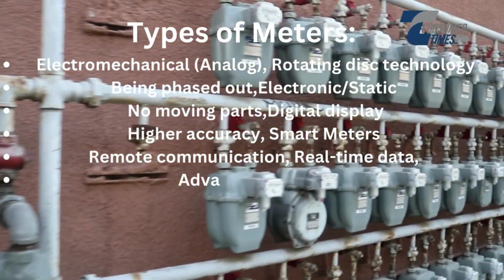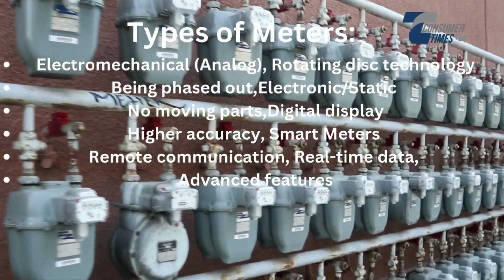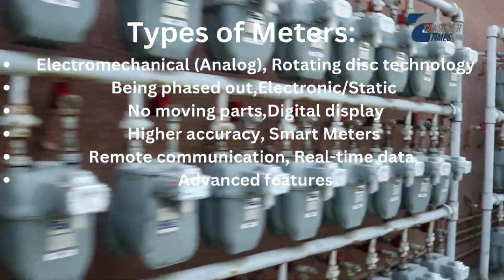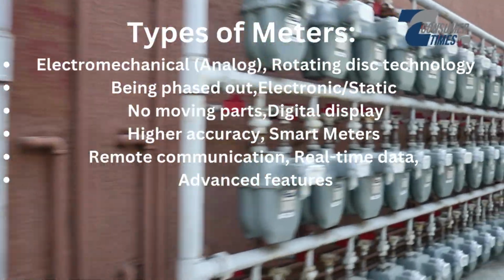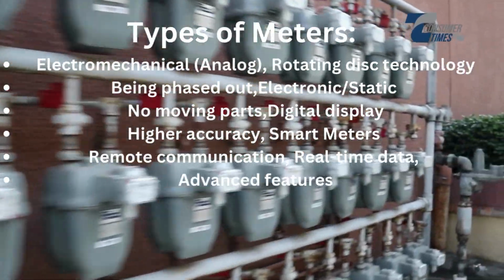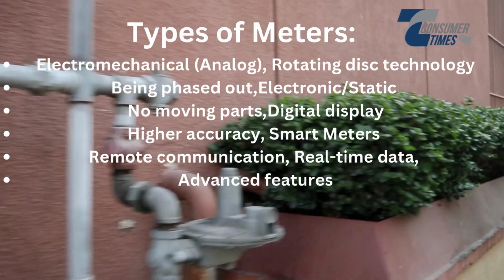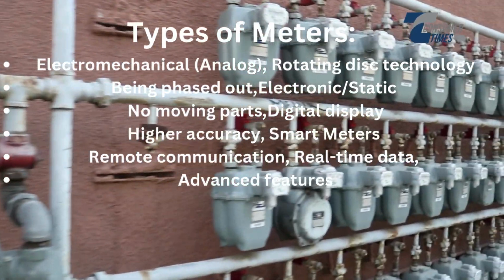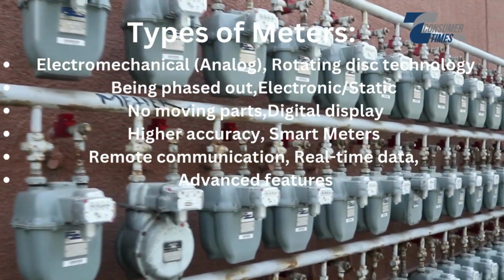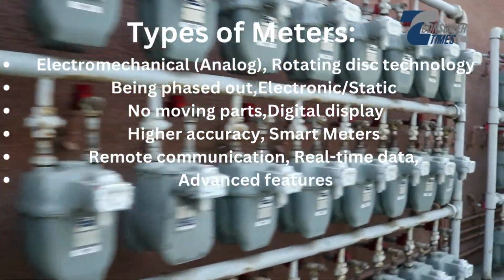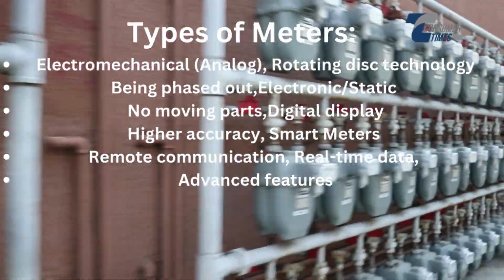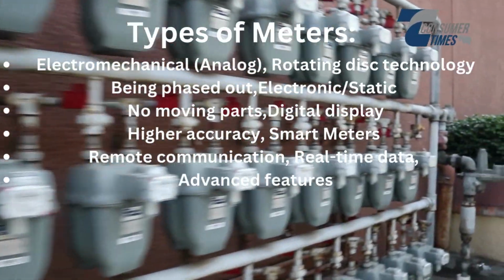This is where periodic testing and calibration become essential. Energy meter testing is a systematic process conducted in specialized laboratories equipped with precision instruments. The testing typically involves several key stages. First is visual inspection, where the meter is examined for physical damage, tampering, or deterioration of components.